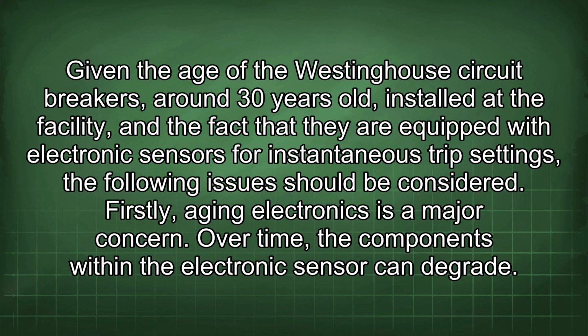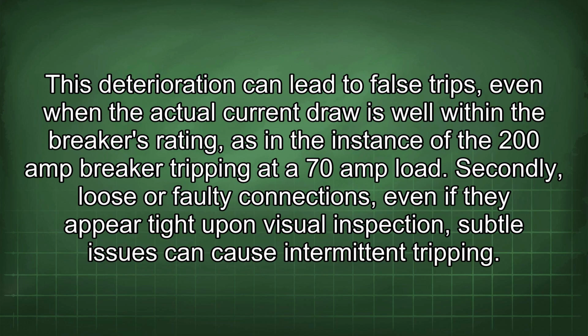Firstly, aging electronics is a major concern. Over time, the components within the electronic sensor can degrade. This deterioration can lead to false trips, even when the actual current draw is well within the breaker's rating, as in the instance of the 200 amp breaker tripping at a 70 amp load.